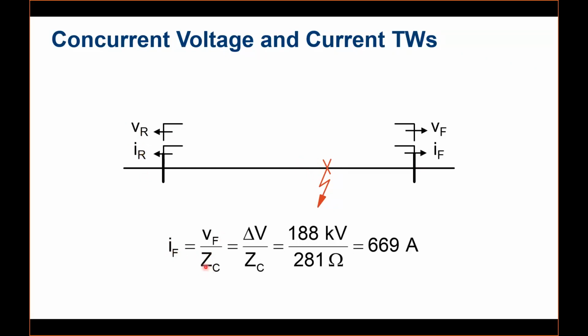ZC is the characteristic impedance of the conductor. That is a known quantity depending on your conductor. Mostly for overhead lines, this characteristic impedance is in the range of 200 to 400 ohms. So for that particular line, you can estimate a step change, or disturbance, in the current of about 670 amps. So we'll be getting two quantities at both ends: the disturbance, or change, in the voltage and also in the current.